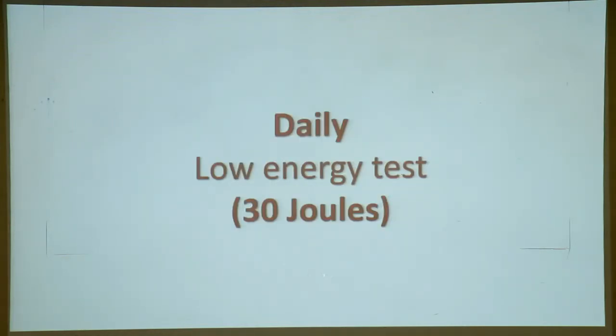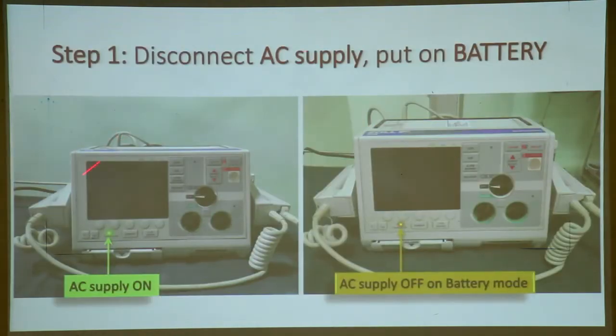Now what is this daily low energy test which you should do? There is an AC power supply; you connect it to the AC power supply, and it will glow green. The moment you cut off the AC power supply, it should work on battery. The battery should be working properly because it needs a change every 6 months. If you have to carry your defibrillator to another place where there is no AC supply, your battery should give the shock. If you only put it on AC supply and do the check, then you can only shock with the AC socket on. Right? You cannot use the battery. So what if it is to be used at a place where there is no AC supply? If your battery is not working, you will not be able to shock. So all the tests are done by switching off the AC supply, and then you have to do this.